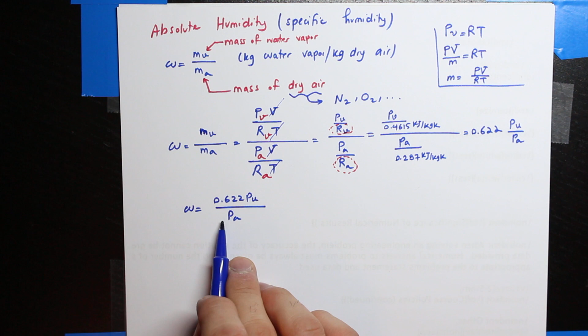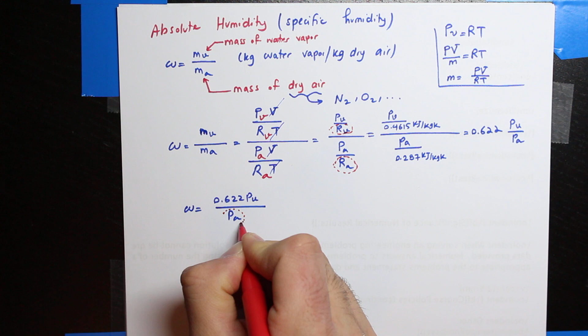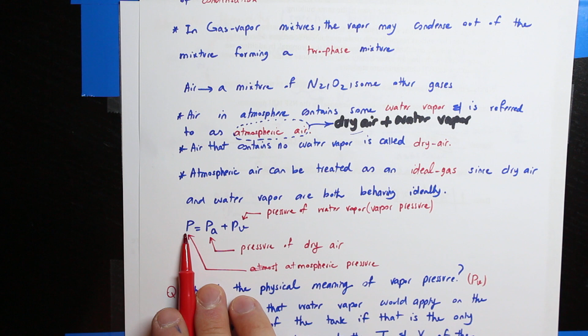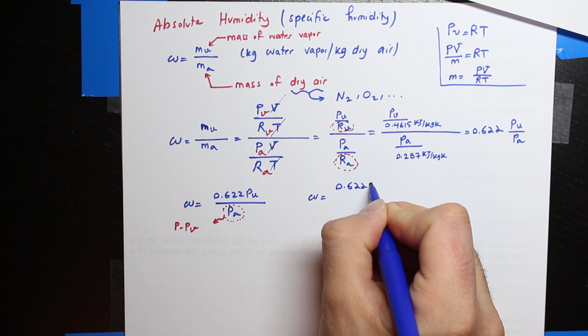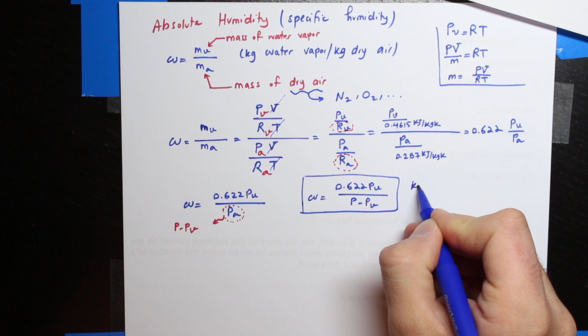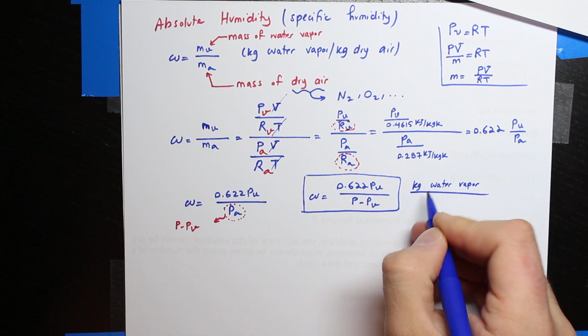Now, there is always a tendency to replace the dry air pressure with P total minus Pv, because on the previous page you learned that the total pressure, or the atmospheric pressure, is equal to Pa plus Pv. So I can find Pa based on the total pressure minus the vapor pressure. So we tend to replace this Pa with P minus Pv. The equation that you will see and use most of the time is omega equals 0.622 Pv over the total pressure minus the vapor pressure. We are using this equation a lot. This is the absolute humidity or specific humidity, based on the pressure. And once again, the unit is mass of water vapor per mass of dry air.